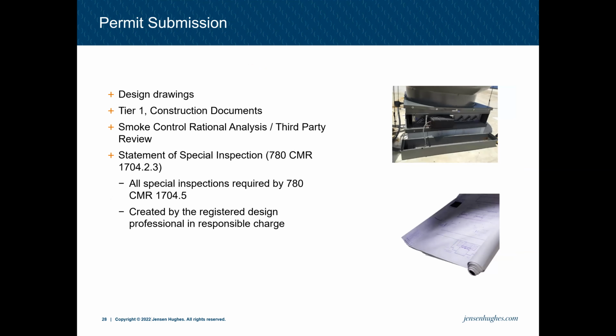Moving through that, for a building permit, you should submit the design drawings, the tier 1 construction documents, which we just went over, the smoke control rational analysis, the third-party review, and a statement of special inspections, which we'll talk about briefly. But the statement of special inspection is required by the building code to be submitted with the permit documents. In 780 CMR section 1704.5 outlines all the special inspections that are required. And this statement of special inspection must be created by the registered design professional in responsible charge for the entity.